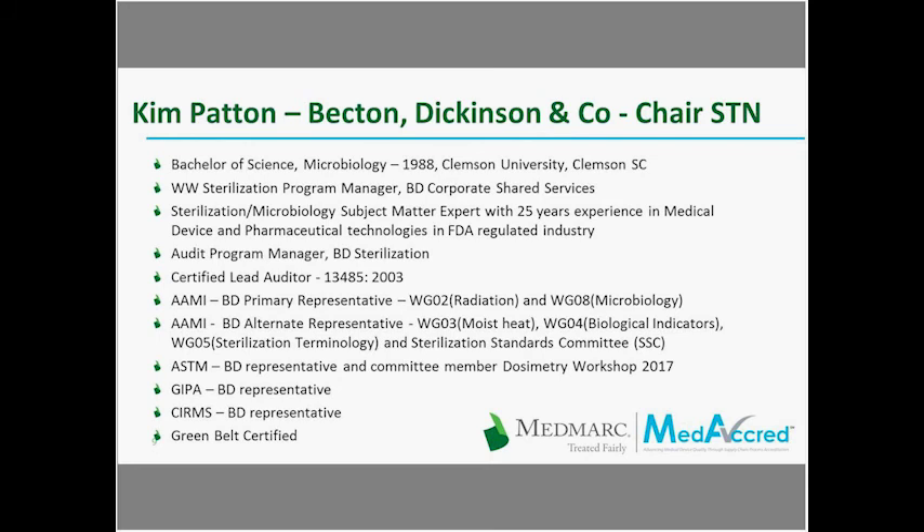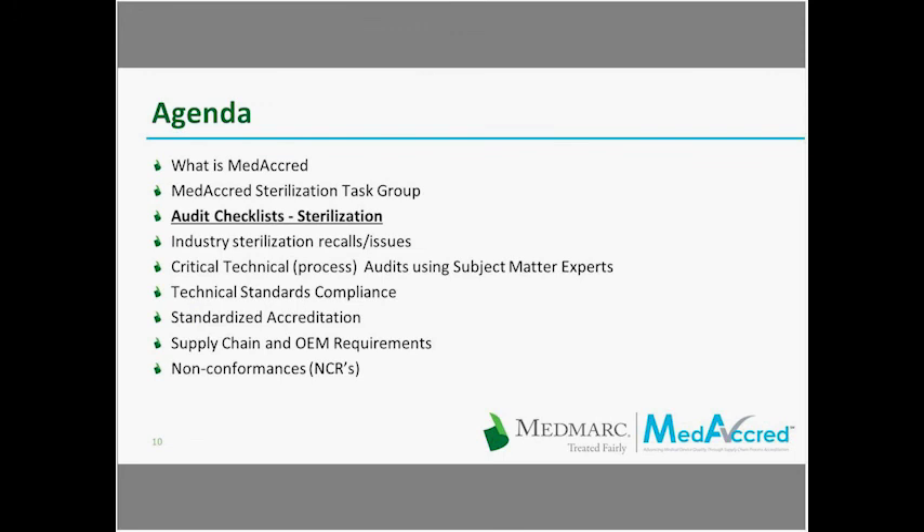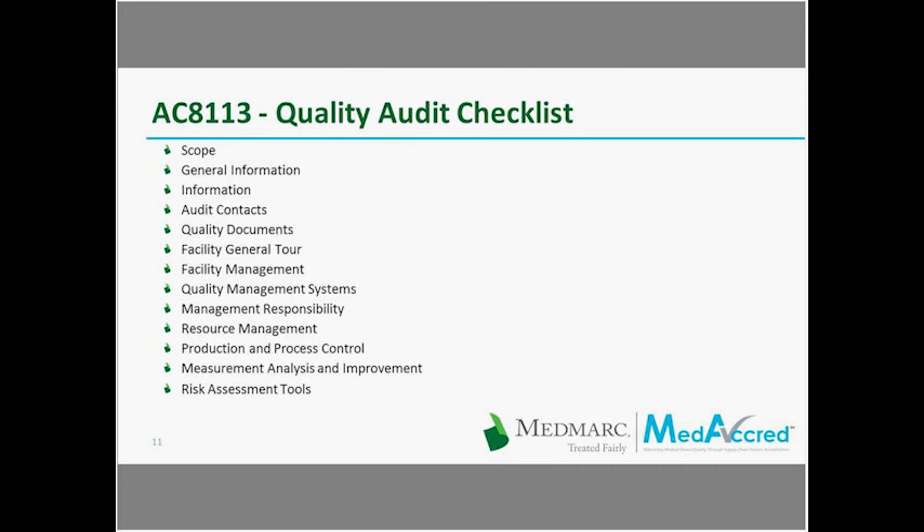Thank you, Mark. I'm going to start out looking at the audit checklists, which are critical to the audit and are completed throughout the process by the MedAccred auditor. For the technical checklists, I'll point out some of the questions to give you a flavor of what they include. First, we'll look at the base or quality audit checklist. This is based on ISO 13485 and 21 CFR Part 820. The checklists are designed for either a yes or no answer, with some questions having an NA option depending on the facility.